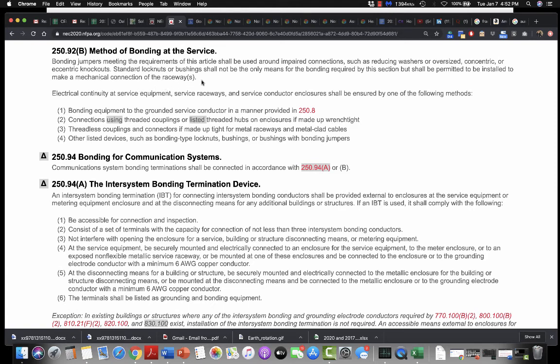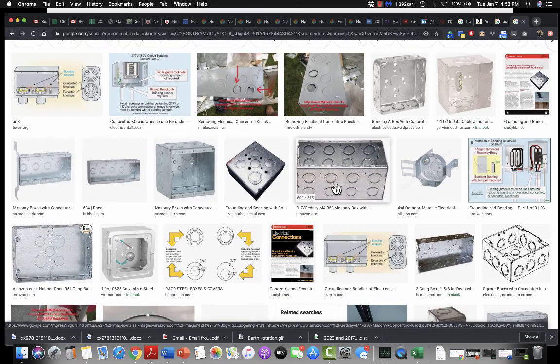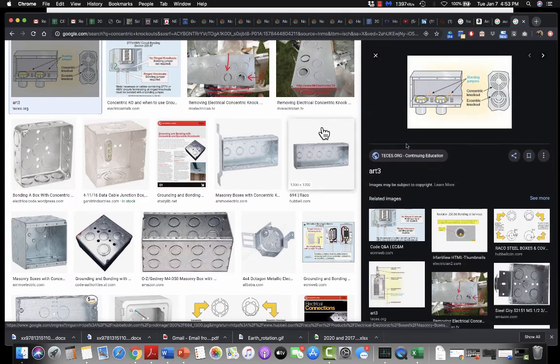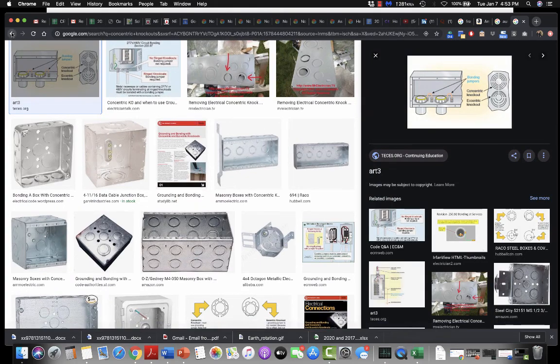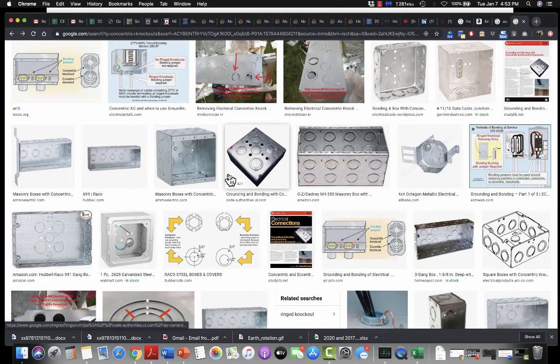So sometimes when you just connect pipe to a box, it can ground things, but when you're bonding to a service or doing a supply side connection, it might not do it just right, especially when you have these extra knockouts. It's sort of like a knockout within a knockout. See what Google says? There it is, knockout within a knockout. So you can select which size you're going to use. And if you still have extra rings that you could have knocked out right there, there's one right there. And if you've got extra ones that you could have used and you didn't use them, then it doesn't work so well for grounding and bonding.